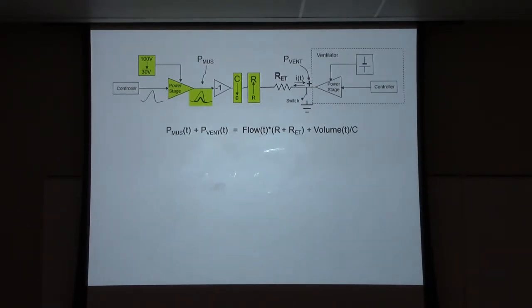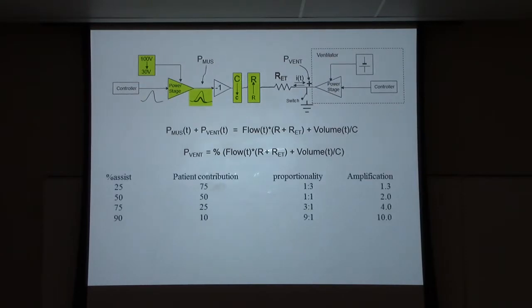All right, so I'm smart. Here. If we tell the ventilator, give me pressure here to be a percent of this term. This term is the total voltage difference from here to here. And we tell the ventilator, and we have all this information, give me a percent of this term. So what will happen if you set this percent at 25%? The ventilator will be giving at any instant 25% of the total voltage. The patient has to be giving 75%.